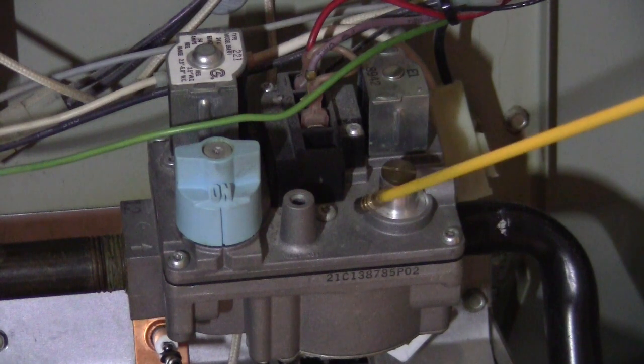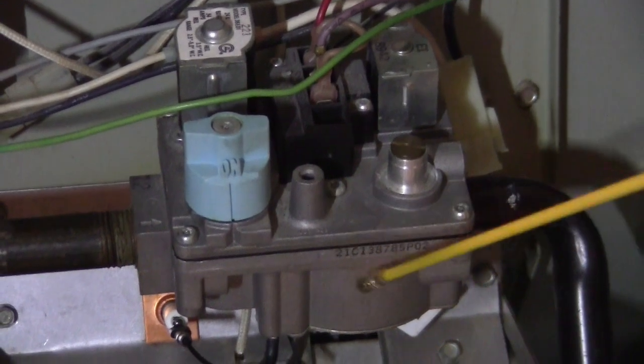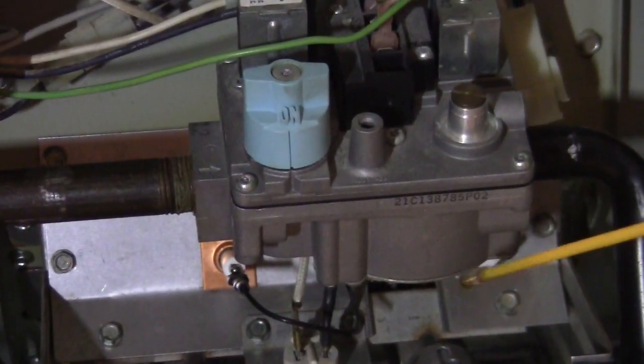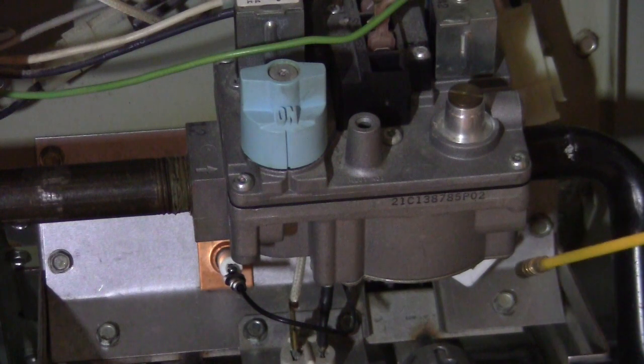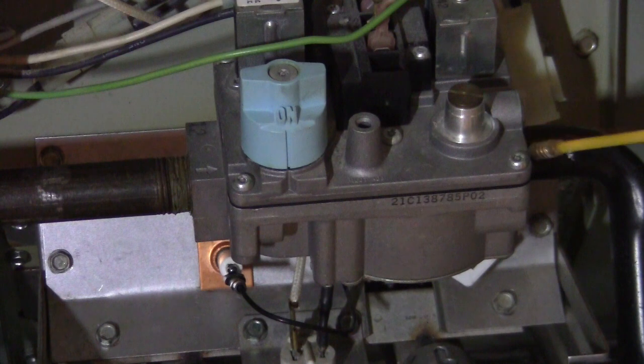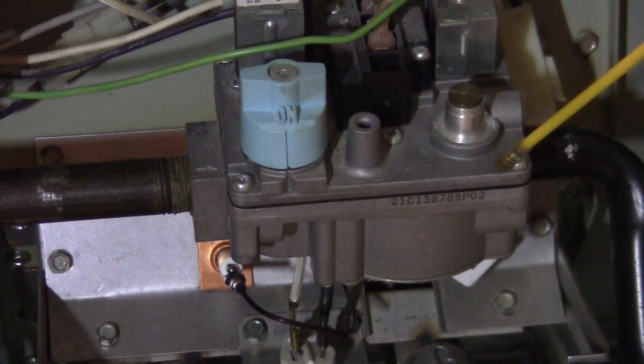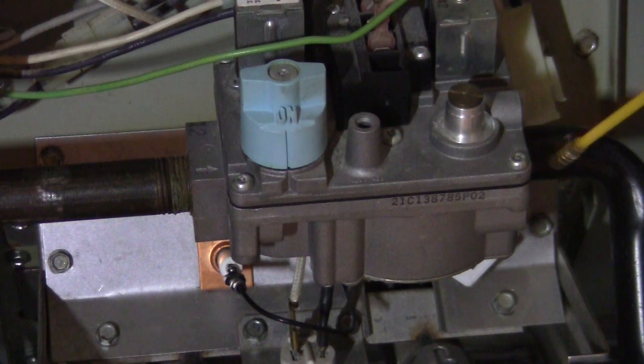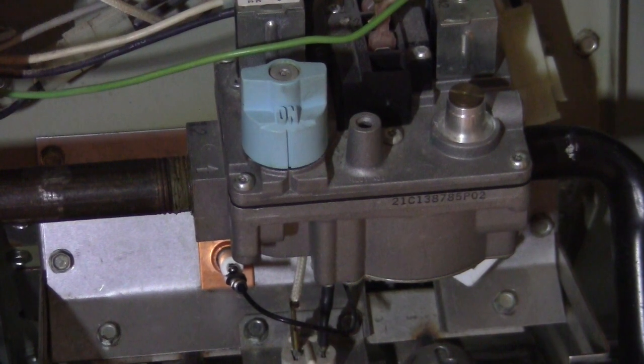If this valve has a problem, if this valve has an issue, and it has to be replaced or diagnosed, I would suggest you hire a professional to do that, because anytime you touch this thing over here, or even the seal over there, it has to be airtight. If you get something wrong, you will have a gas leaking issue in the home. And if the leak is very slow and very small, it is even worse. You don't even know you have a gas leak. You might cause a big problem.